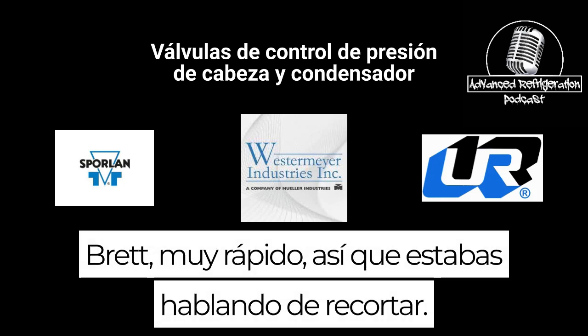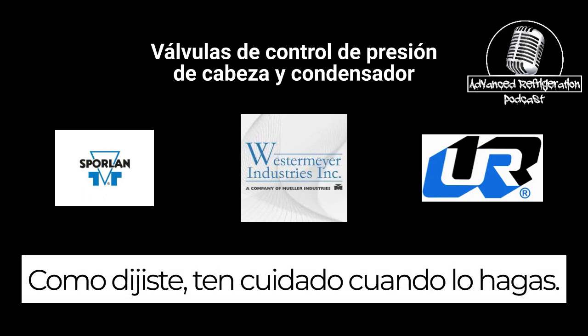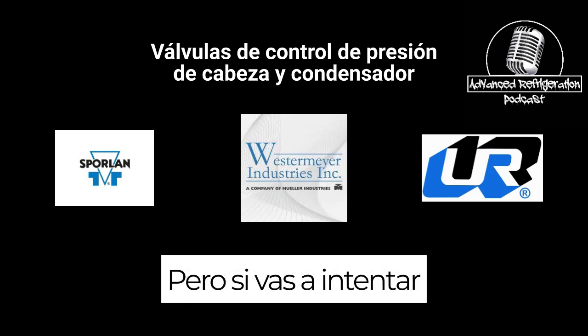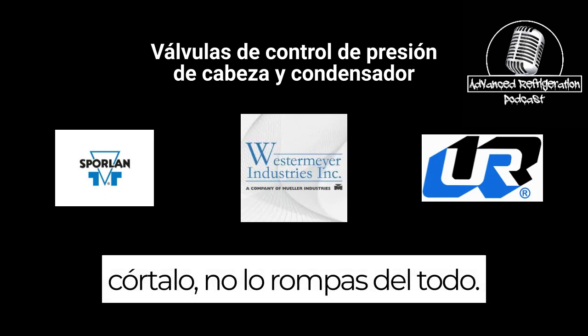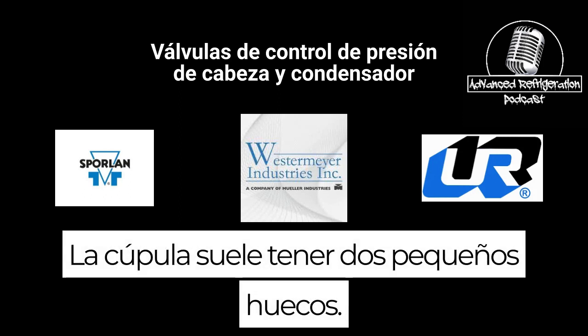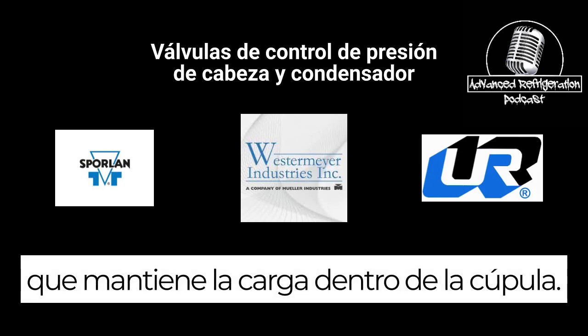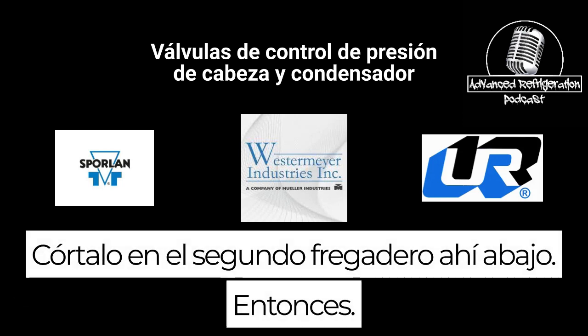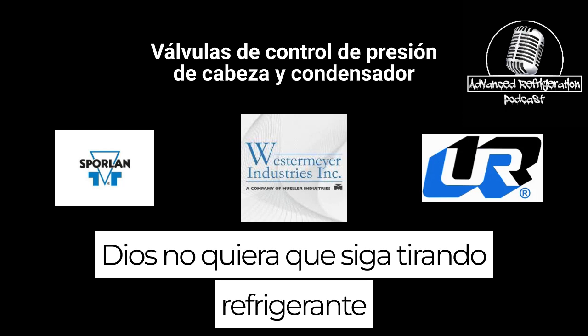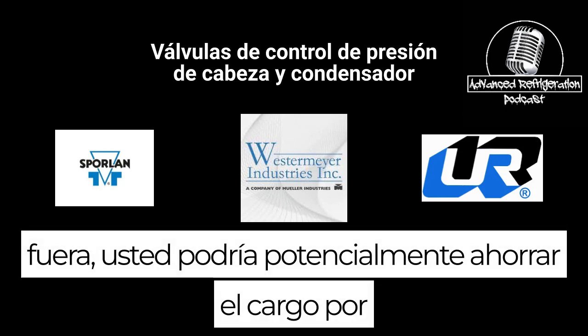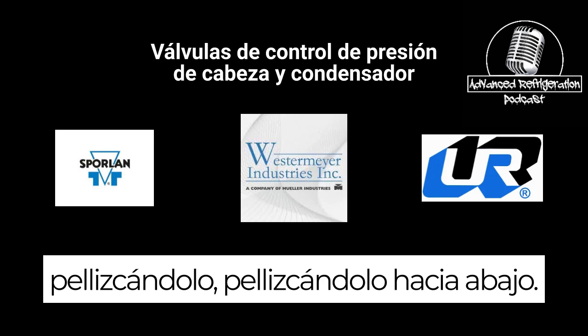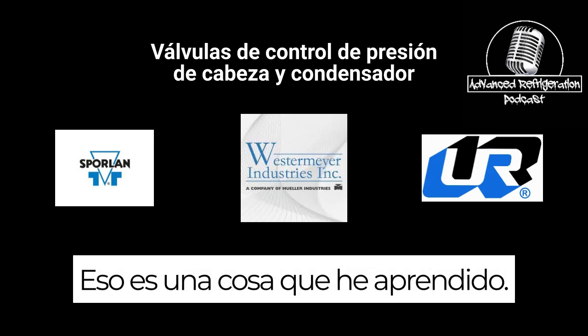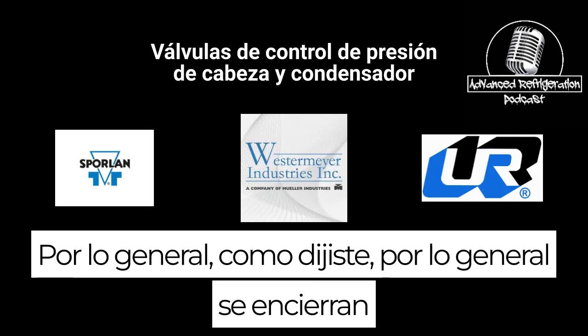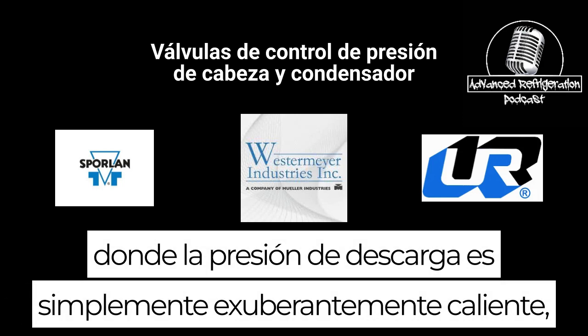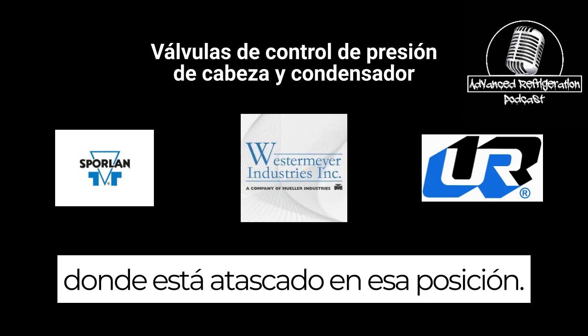So you were talking about clipping. Like you said, be mindful when you're doing it. If you are going to try to clip it, don't break it all the way to the dome. Usually there's two little divots in it that keep the charge inside of the dome. Cut it up to there, leaving the second tank down there. So if, God forbid, it does continue to dump refrigerant out, you could potentially save the charge by pinching it back down. That's one thing that I have learned. Usually, like you said, they lock up where the discharge pressure is just exuberantly hot, stuck in that position. Be mindful.